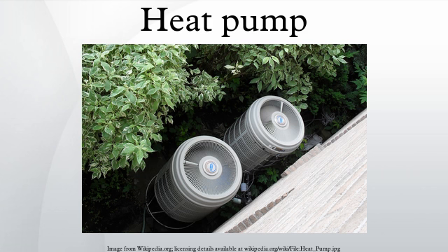Heat sources and sinks. By definition, all heat sources for a heat pump must be colder in temperature than the space to be heated. Most commonly, heat pumps draw heat from the air or from the ground. The heat drawn from ground-sourced systems is in most cases stored solar heat, and it should not be confused with direct geothermal heating, though the latter will contribute in some small measure to all heat in the ground. True geothermal heat, when used for heating, requires a circulation pump but no heat pump, since for this technology the ground temperature is higher than that of the space that is to be heated, so the technology relies only upon simple heat convection.